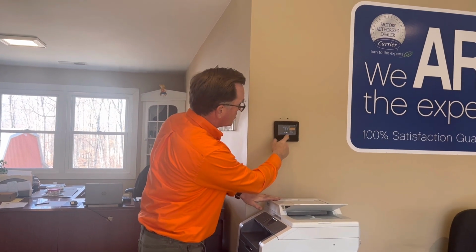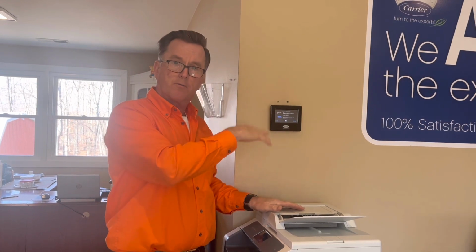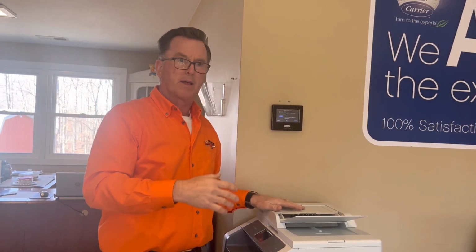But this is the Infinity control here. You can also tap on that and you can actually reset the fault. Another way you can reset the fault is, once you've cleared and fixed the issue at the indoor equipment, you can power cycle the equipment, turn it off and turn it back on. The Infinity also will try to reset itself on its own. After 4 hours, it'll try to reset the fault and restart, if this happens when you're not home, for example. That's often with no heat situations.